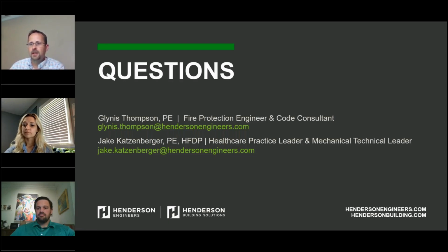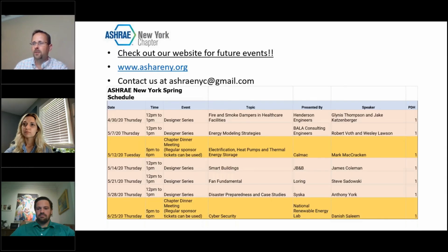Fire dampers, in my understanding, I did some research just last year trying to find a fire damper that could be overridden, and they didn't have one that I found. And so you had to use a fire smoke damper if you had a damper that you needed to override for a smoke control system.